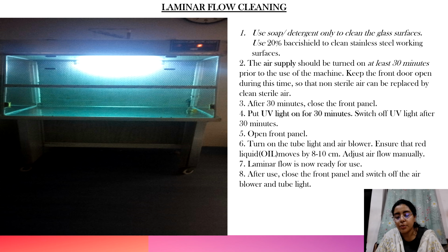Ensure that the red liquid, which is the oil, moves by 8 to 10 centimeters or is in that specific range, which ensures its adequate usage. Adjust airflow manually. Laminar flow is now ready to be used. After use, close the front panel and switch off the air blower and tube light, and we have to clean following the same procedures as discussed above.